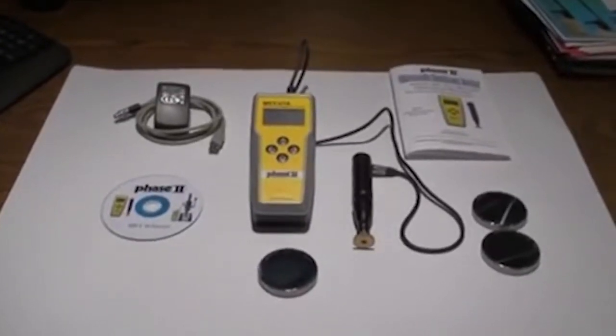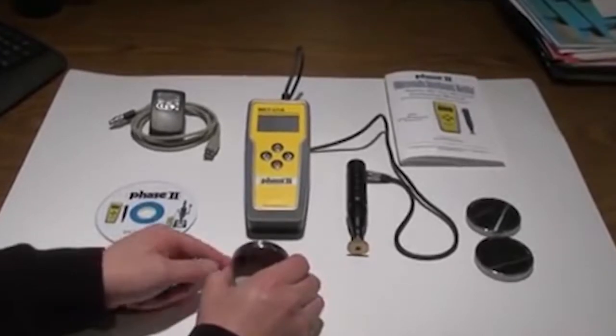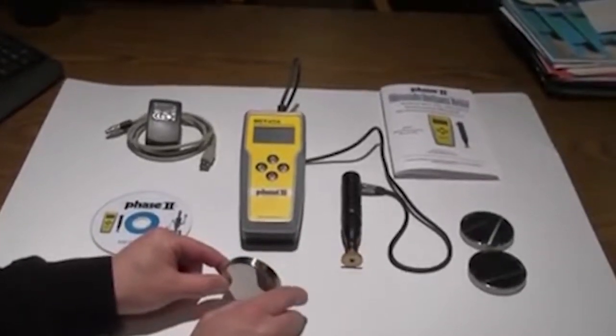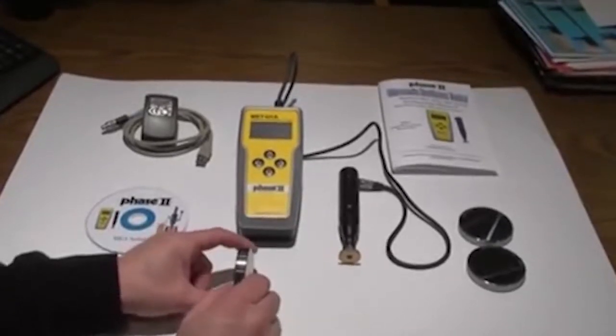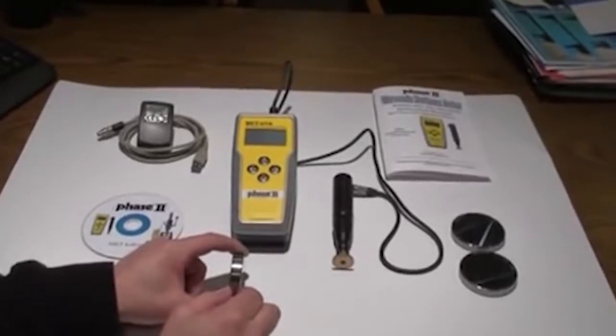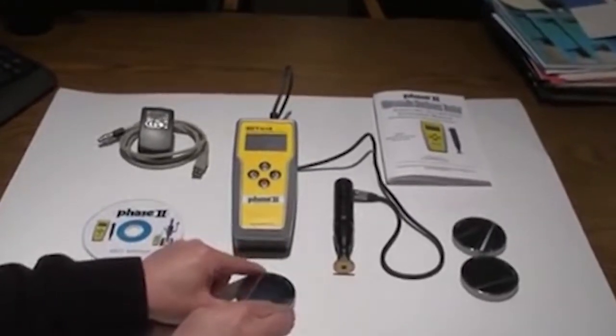Certain workpiece parameters must be met for the UCI system to work properly. The minimum radius for a test is 5 millimeter. The workpiece needs a minimum thickness of approximately 1 millimeter. However, in the field without support, that number may vary up to 2 millimeter depending on the material being tested.